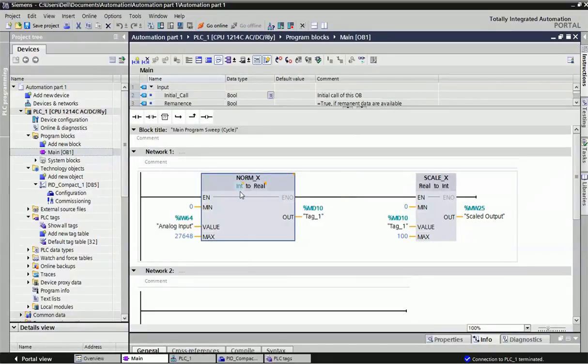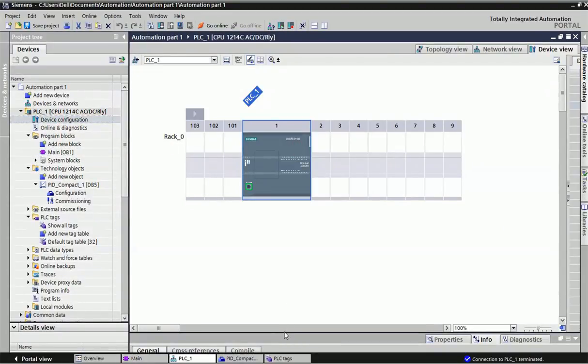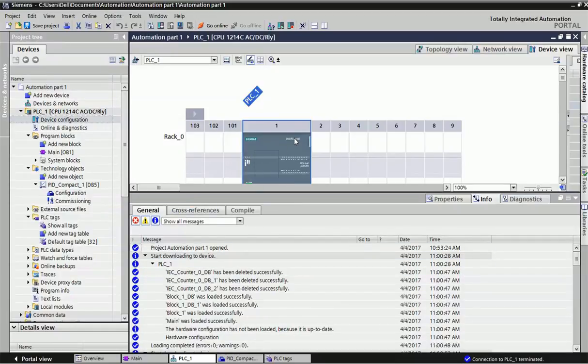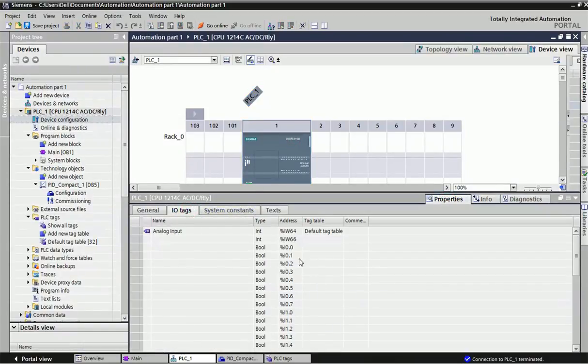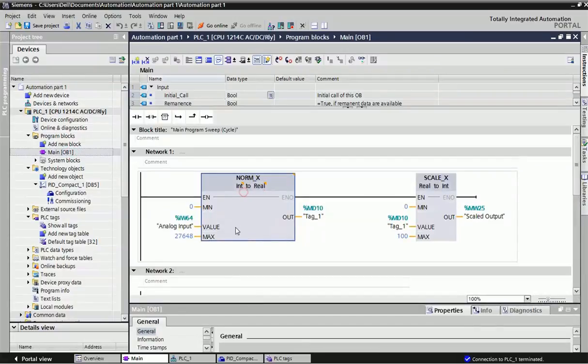We are giving input IW64 here, because in S7-1200 PLC, the input analog addressing starts from IW64. That we came to know from the input-output addressing. Here you can see two types of analog signals: IW64 and IW66. I have assigned IW64 analog value, with the minimum and maximum range of the raw value. This value we are getting in real data type, 32 bits, so I have assigned memory double word to store the data.